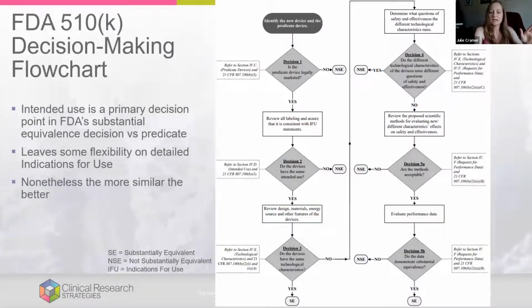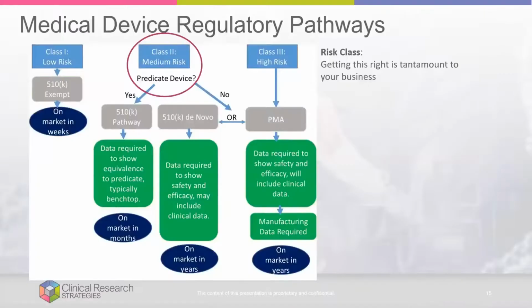All right. So what does the FDA have to say? Is that 510K something that you can resubmit, or do you get one predicate device that you can compare yourself to and you submit it one time? And if you get rejected or denied, then you have to go down to class 3? I don't know that it does start the conversation, and I do believe you get a chance to resubmit, or you can always submit a brand new one, referencing your old one. And it's just one predicate device that you're comparing yourself to. You can't compare yourself to a few.